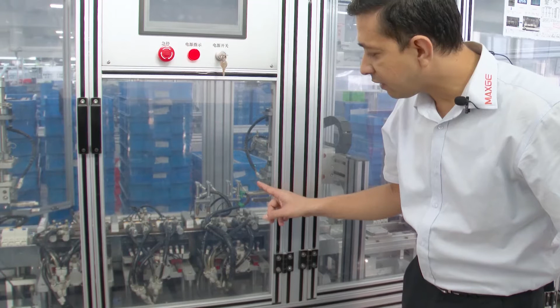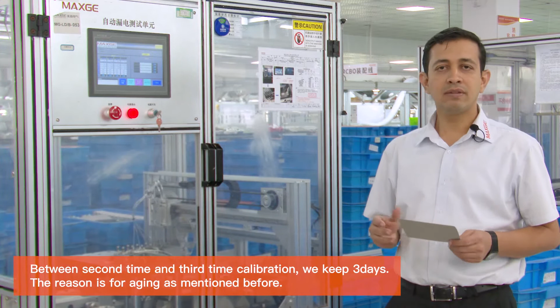Now we are at the third calibration. Between the second and the third calibration, there is a gap of 3 days. The reason is the same as I told you, the aging. And after the third calibration, we can be 100% sure that the RCCB will perform its job in any condition across the world. So the process is the same: we apply the residual tripping current and the RCCB trips, and we check whether the RCCB is tripping normally or not.